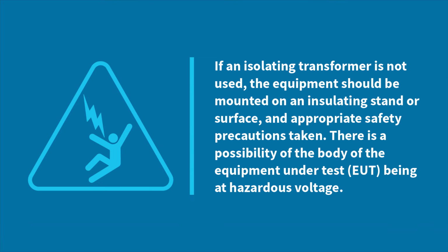Safety precautions. If an isolating transformer is not used, the equipment should be mounted on an insulating stand or surface and appropriate safety precautions taken. There is a possibility of the body of the equipment under test, EUT, being at hazardous voltage.